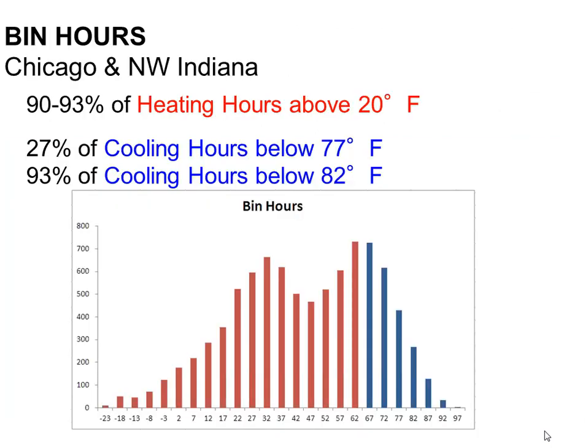And then just to show you graphically here, all these bars in red represent the number of heating hours that we have for 5-degree temperature bins. So if I pick one of these lines here, like this one right here, 32 degrees, if I look up that 5-degree band right around 32 degrees, so from 30 to, we'll say, 35, it's like 650 hours. The 37-degree band's another 600 hours. So you can look and see the bulk of the hours are between 20 and 60 degrees, the most red bars here.